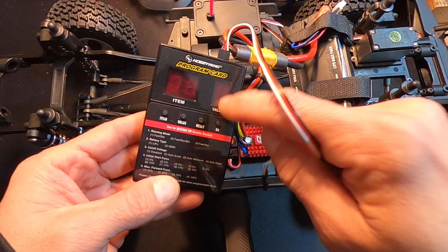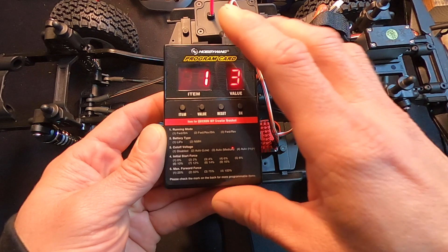So for the WP1080 and the programming card, the LED programming card, there are 2 plugs on top. You use the one on the right, the one with the funny little squiggly thing on it, that goes to the white wire, and the other end plugs into the speed control right on top, the fan port or programming port, whatever you want to call it. Turn the speed control on, the lights come on and off for a second, and then you get the numbers. Item is the number along the row, and value is the setting itself.